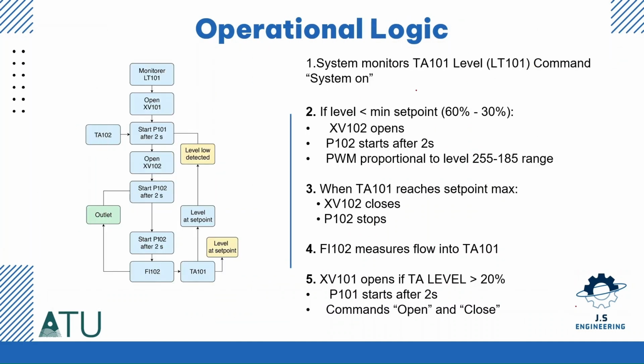The system follows simple rules. The ultrasonic sensor checks the water level. If the level drops too low, the valve opens and after 2 seconds the pump starts refilling. So if the level is below, for example, 30%, which is the set point, the solenoid valve XV102 will open. And then after 2 seconds, the pump 102 will start and the PWM is proportional.